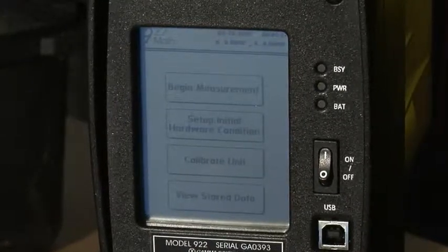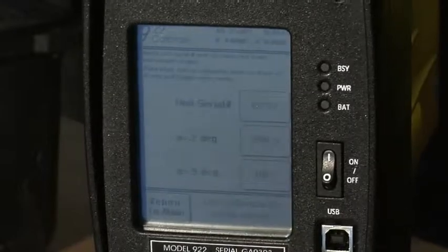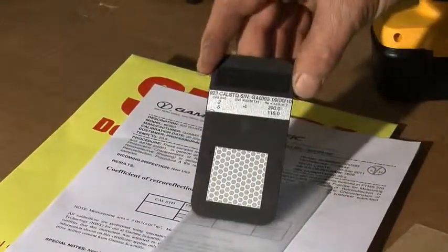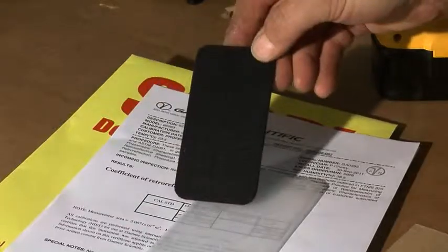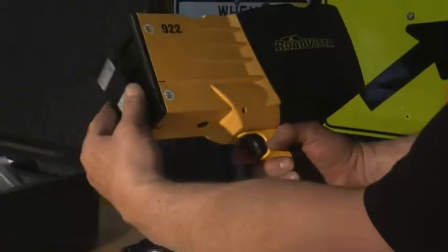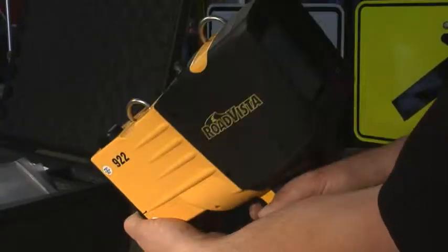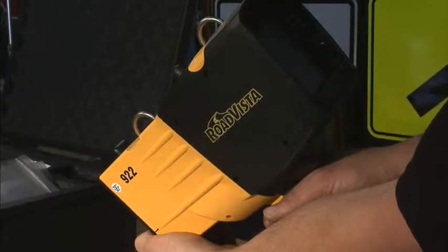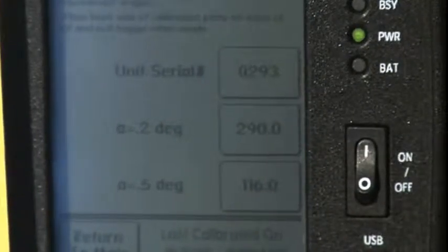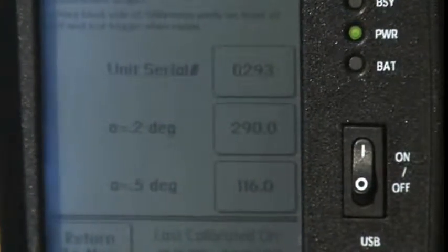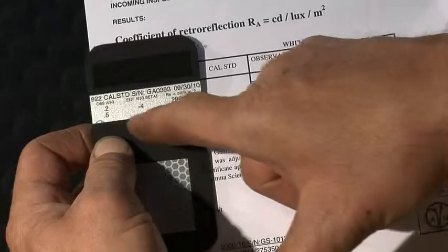On the opening screen, press Return to Main. To view the main menu, choose the Calibrate Unit option. Remove the calibration standard card from its protective cover. Handle the card by its edges, being careful not to touch either face of the card where it is measured. Verify that the calibration values and the serial number displayed on your screen match those on your calibration standard card.